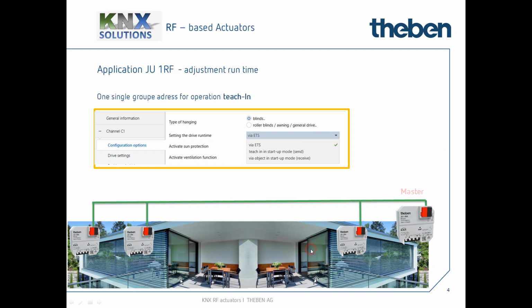That means you have here a master. This master sends its running time to the slaves, and the slaves here are set to receive the value. You start the teach-in by sending a bit object, and you stop the teach-in by a 0 command. The running time you do manually: you press a push button, the blinds run down and the time is counting. When you're at the bottom end, you stop the drive, and this time between the upper position and the lower position is finally shared and sent to the slaves in your project.